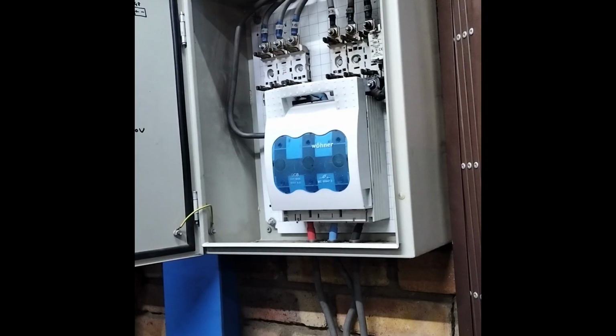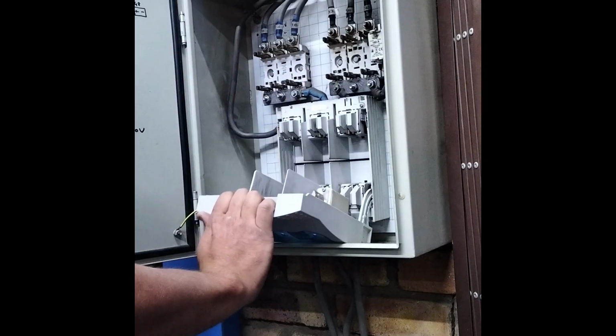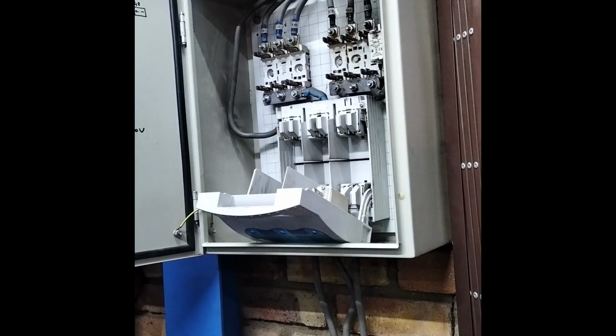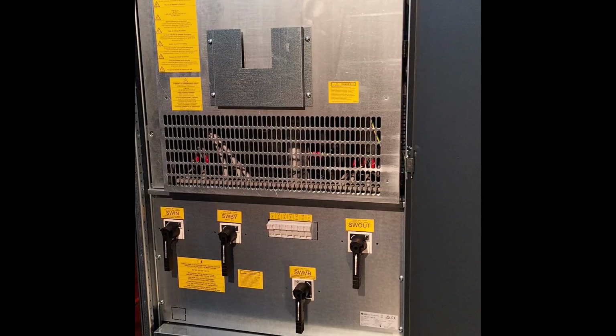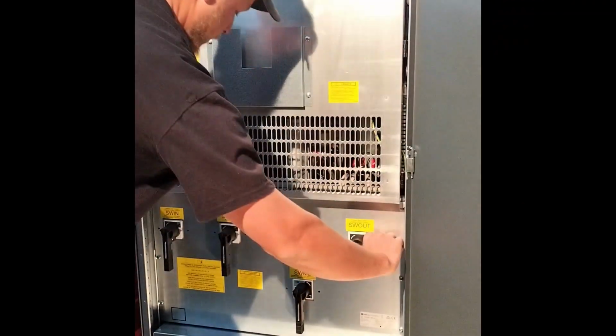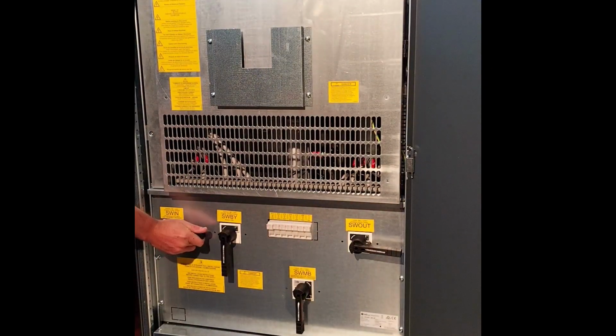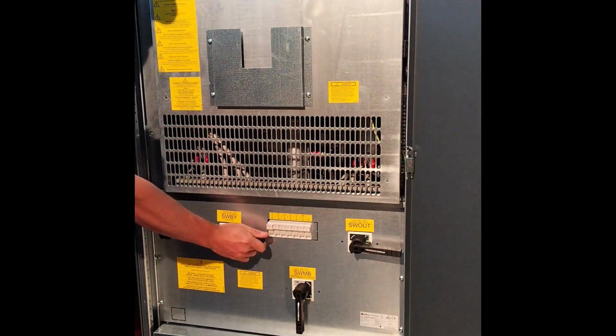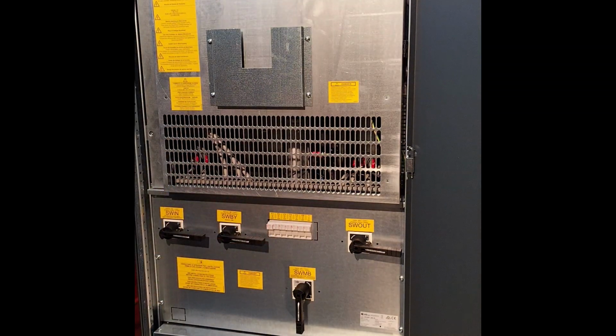For the power down procedure, we start with the batteries and we isolate the batteries from the UPS. Output is switched off next. The main rectifier supply is turned off next. Now the bypass supply is turned off, and this completes the power down process.